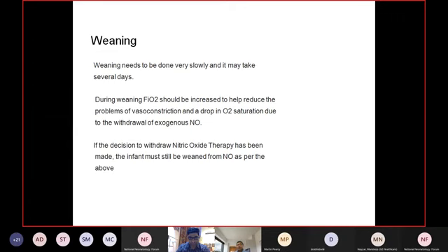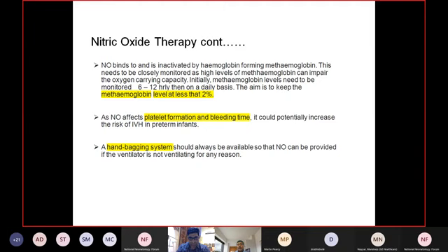There are a few things: it's a costly system. As I have said, in this system the NO and NO2 sensors you need to change every year. These are very costly sensors. These are not like oxygen sensors. These sensors cost around 50,000 rupees per sensor, so you can understand that that itself will be a cost of about 1 lakh rupees per year. So over a period of say 7-8 years, this is a significant cost.